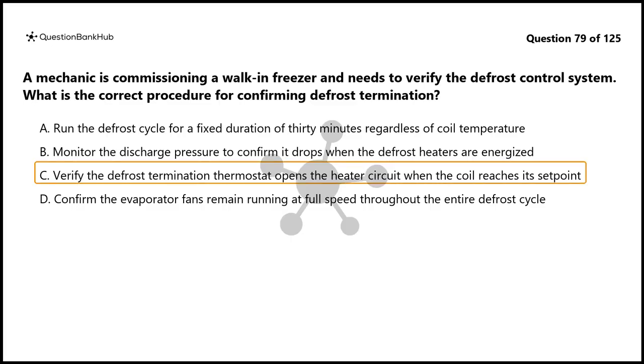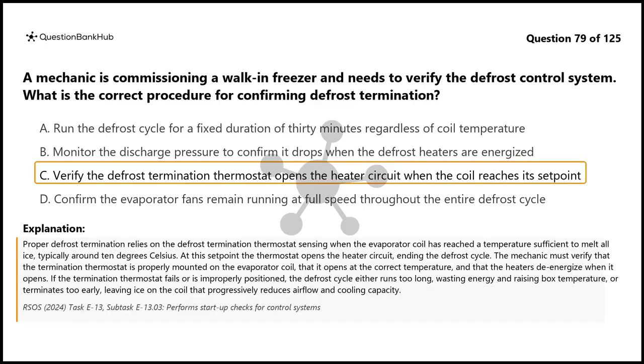The correct answer is C. Proper defrost termination relies on the defrost termination thermostat sensing when the evaporator coil has reached a temperature sufficient to melt all ice, typically around 10 degrees Celsius. At this set point the thermostat opens the heater circuit, ending the defrost cycle.